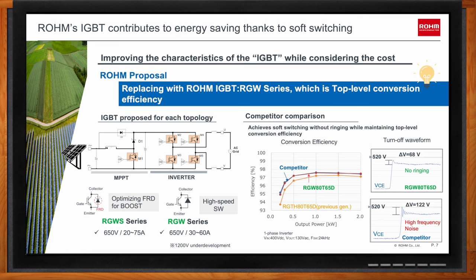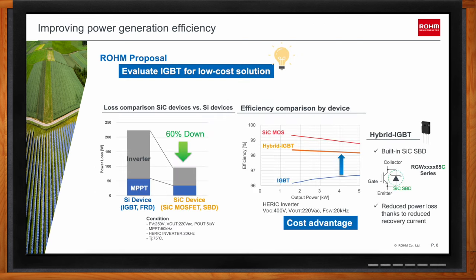Compared to Silicon devices, SiC MOSFETs have about 60% less power loss, meaning higher efficiency. However, SiC devices cost roughly double that of IGBTs. This is why it's worth evaluating IGBTs alongside SiC MOSFETs. Rohm's RGW series also includes products with a built-in Silicon Carbide Schottky Barrier Diode — known as a hybrid IGBT — which achieves efficiency closer to SiC MOSFETs.